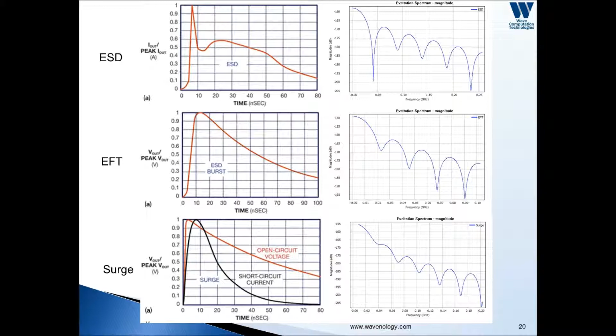In summary, the 6 types of IEC test standard we referred has 3 key parameters for us to understand. Number 1 is the pulse time window, ranges from 2 nanoseconds to 1000 nanoseconds. Number 2 is their bandwidth in the spectrum, ranges from 25 MHz to 2000 MHz. These 2 parameters are very typical in describing the excitation pulses. There is a third important parameter to characterize the excitation pulses, which is not quite often being aware of. That is the spatial wavelength that the pulse will excite. The wavelength can be calculated by dividing the speed of the wave with the frequency of the signal.